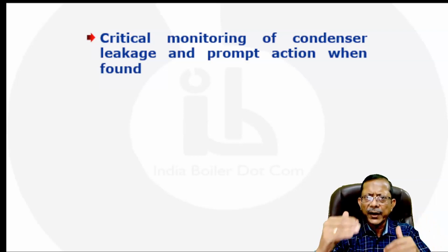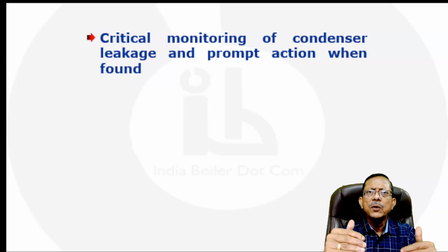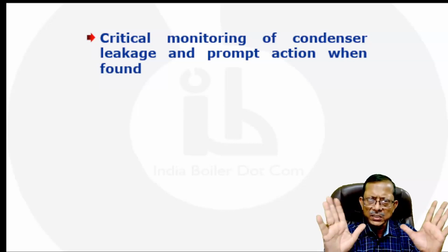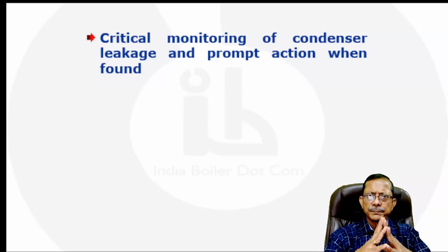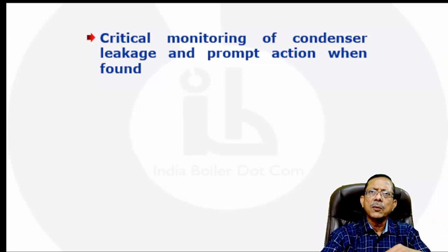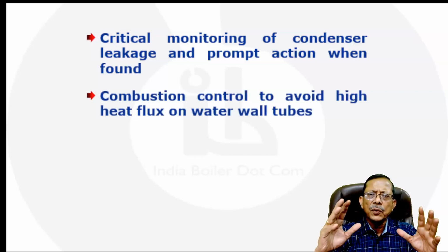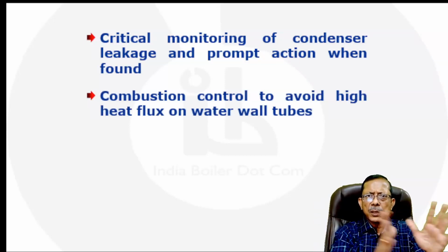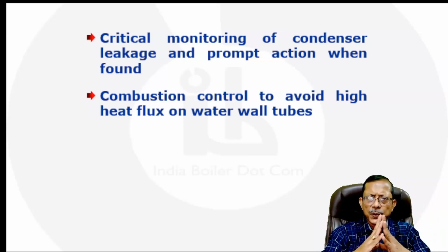And whenever you find a condenser leakage, you have to take precautions, right? Immediately you have to go for the blowdown, find the source, stop the source, or go for a shutdown in the worst cases. Chloride is not acceptable in the system. Okay? And taking care of this caustic and chloride, now let us say that I have to take care of the overheating condition, because the corrosion and overheating both are causing this problem.